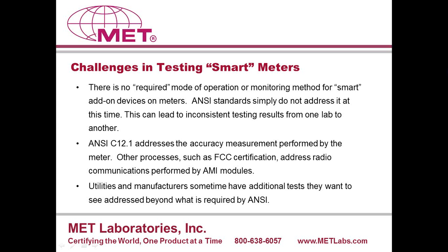Also, the utilities and even manufacturers sometimes have additional tests that they want to see addressed that go well beyond the ANSI standards. Again, not everything is in the C12 standards, and there are a lot of problems that will arise in the field, and unfortunately, many times that's after a certain number of products have been deployed and you start seeing some reoccurring events and problems. During the course of a test program, you may want to extend, for example, a MET certification program to address some of these other issues that you're seeing in the field. The MET certification program is a very flexible program. It's not rigid. It's only rigid in the fact that you need to test to all the ANSI requirements, because that's what everyone is asking for. And you need to meet certain criteria in order to become certified, quote unquote, at MET Laboratories. But beyond that, there are also optional tests that can be performed.